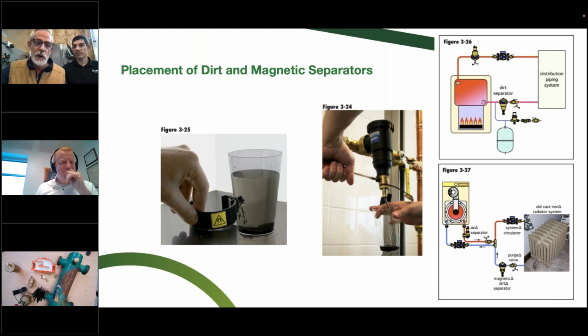Sometimes referred to as boiler ink. If you're taking a sample like in the picture there and it comes out looking gray or black in the worst case, most of the time kind of gray, it's got a tint to it, and you say, oh, it's just dirty water from touching all the metal in the system. Well, actually, set that on the counter overnight and come back the next day. If it looks like the cup in the picture there, it's magnetite. It's not just dirty water from touching cutting oil or whatever is in the system.